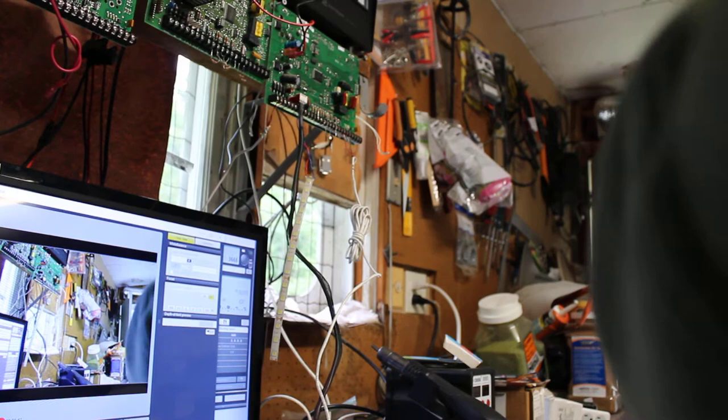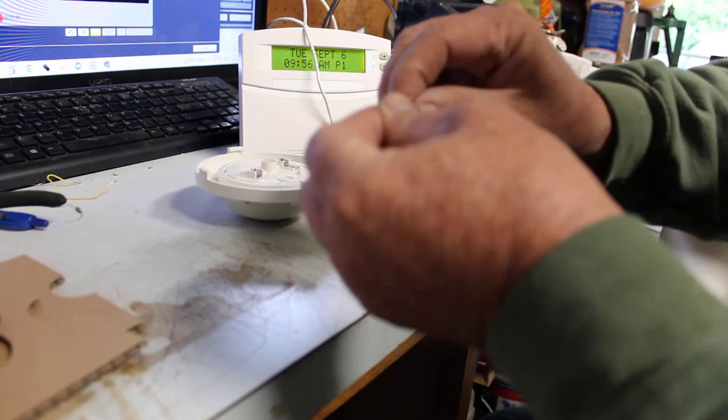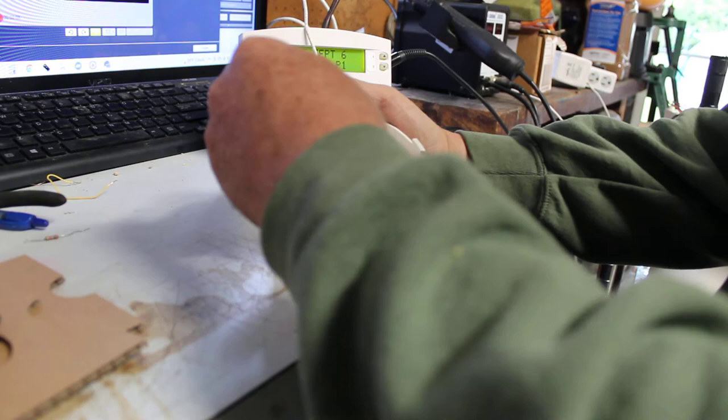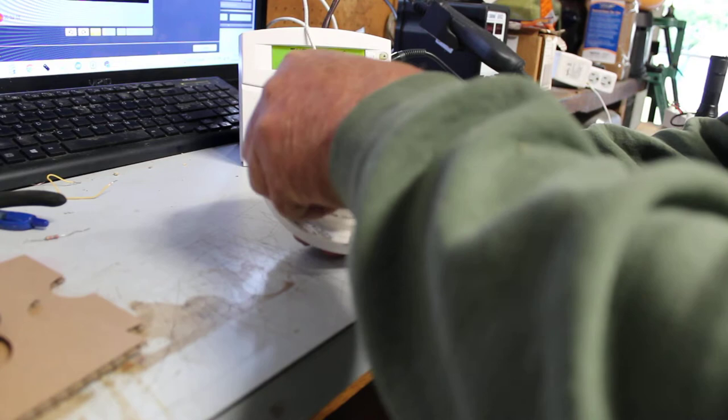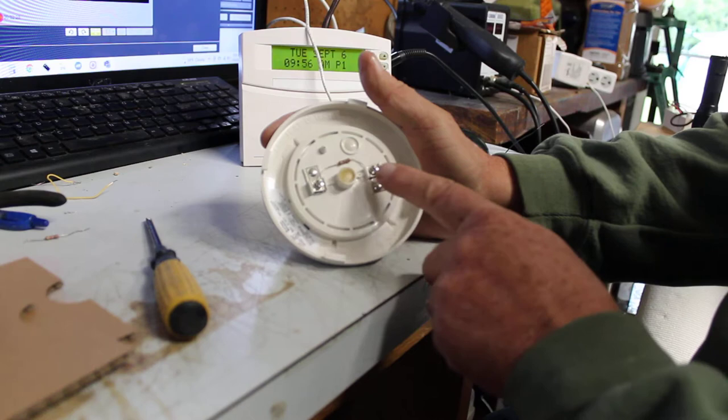Let's bring this back down. The first thing we're going to do is wire it up. I got a resistor here, this is the resistor that belongs up on zone 8. What you have to do down here on this rate of rise is you got to put the resistor across the circuit. Fire alarm systems are normally open where most burglar alarm systems are normally closed. I'm not going to get into that either.